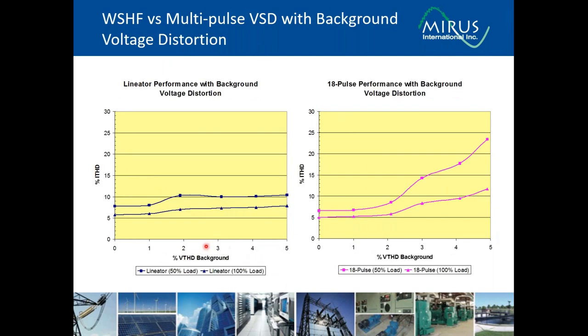Also with background voltage distortion, you can see if we introduce 0 up to 5% voltage distortion, the wide spectrum harmonic filter here stays at just around 5% current distortion with no background voltage distortion. All the way up to 5%, we were still under 8% current distortion. That's full load. At 50% load, you can see the performance also held up fairly well.